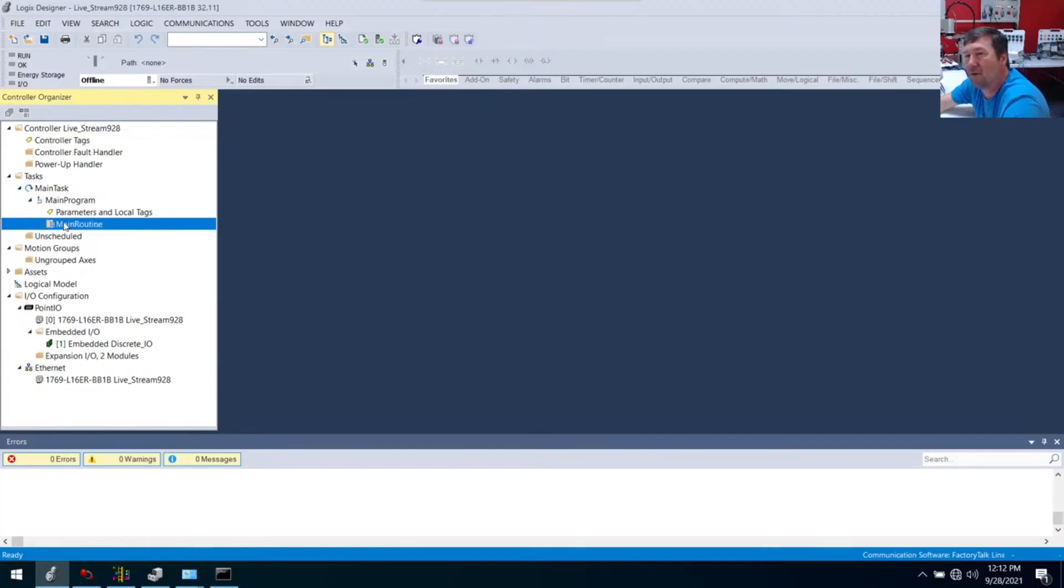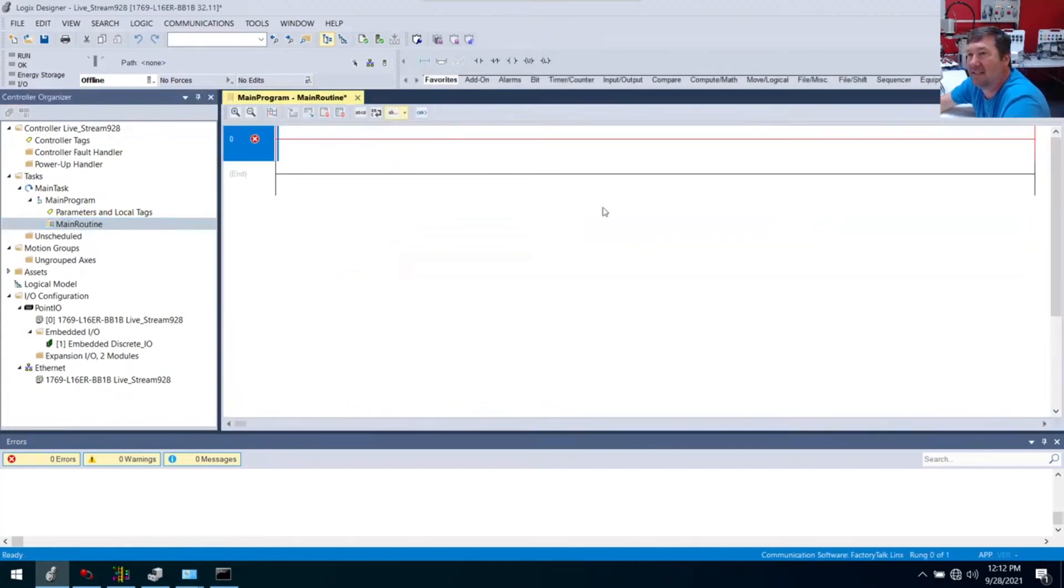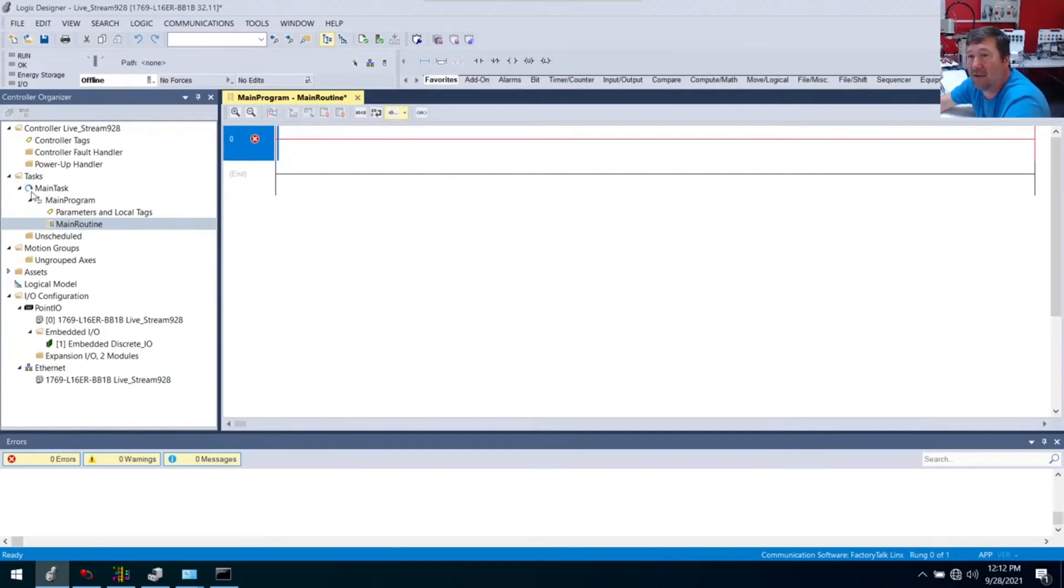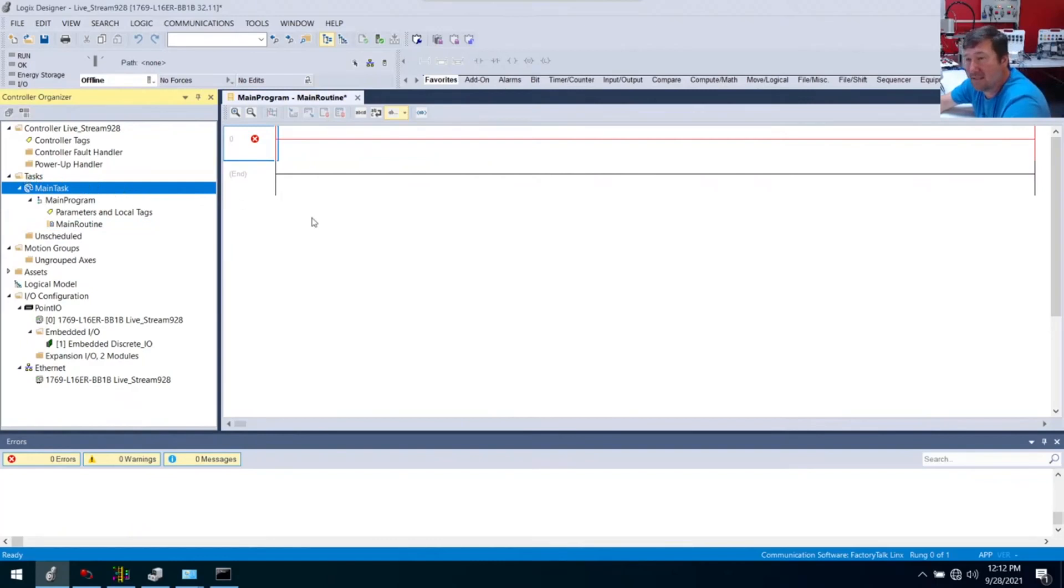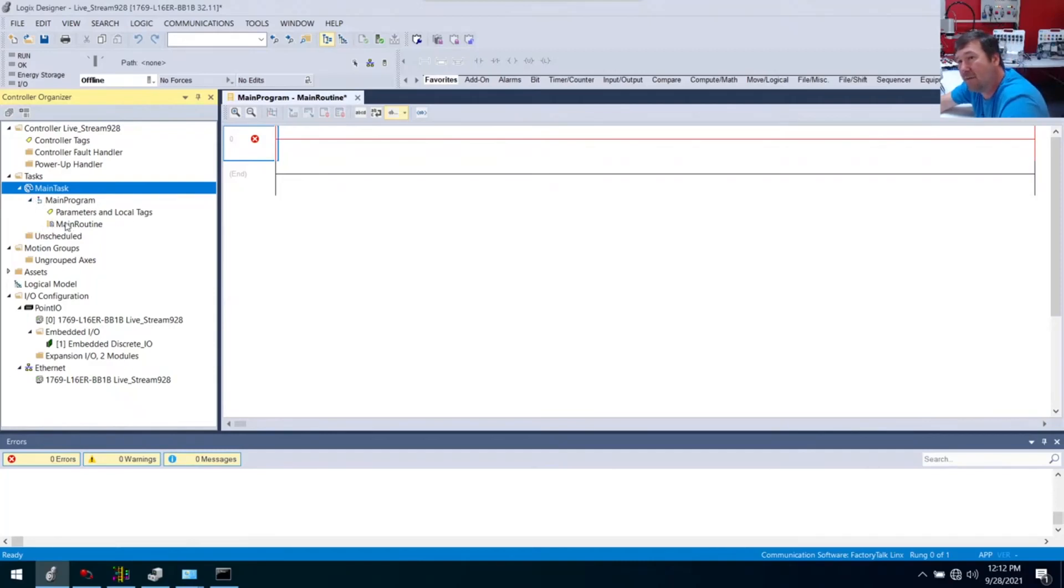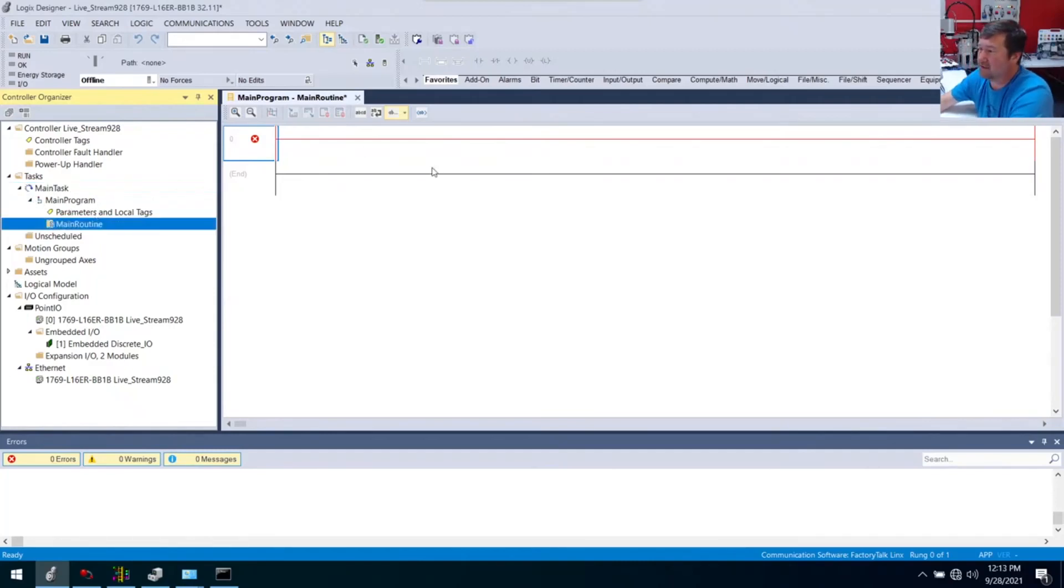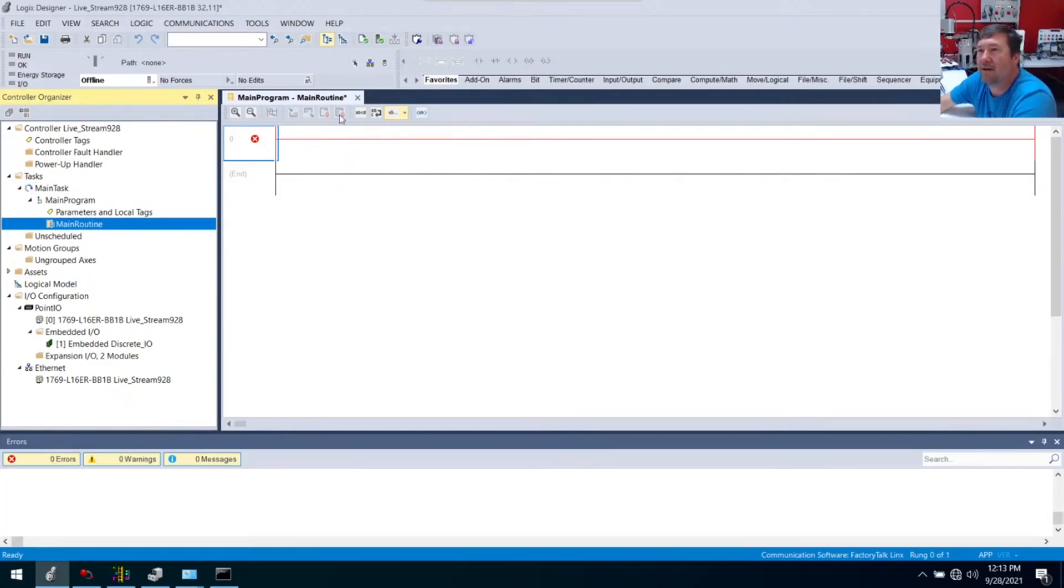What I always tell everybody is you can kind of follow down task and just keep hitting the arrows into it, and eventually you're going to find the main program. This is the program that is going to be run by default. A little really quick spiel about task: we have a continuous task and that thing runs as fast as it can. As soon as it's done running, it goes and tries to run again. Inside of it we have programs, and mainly inside of it we have routines.